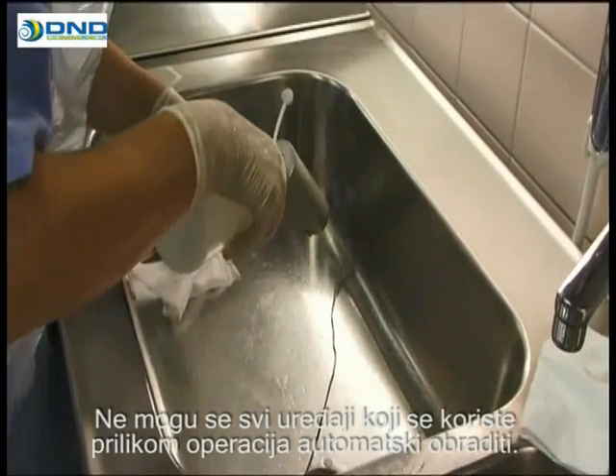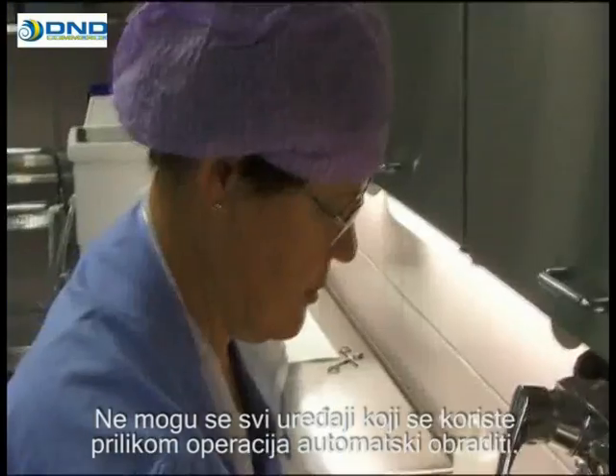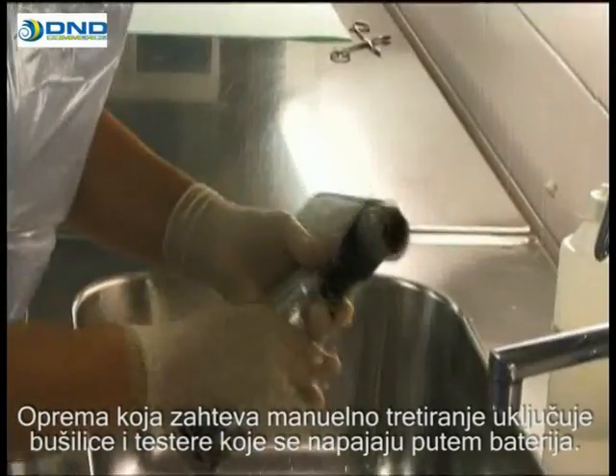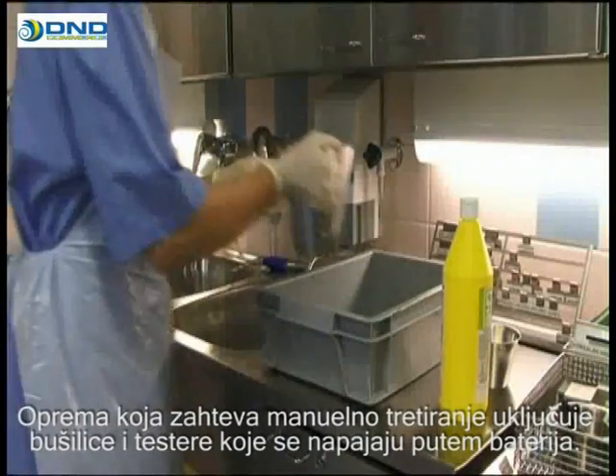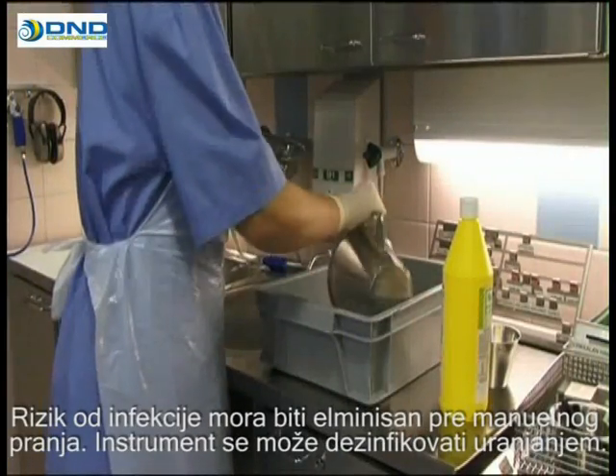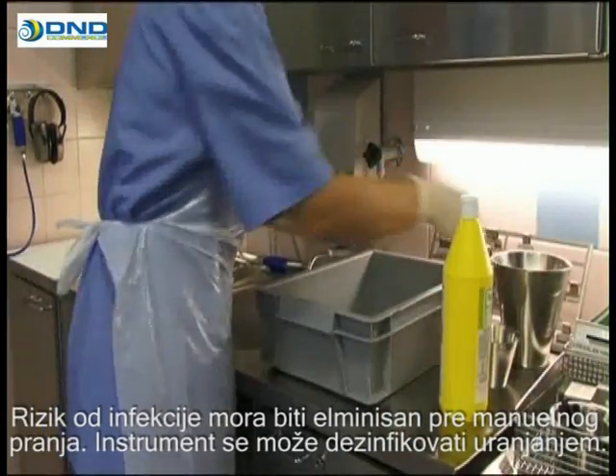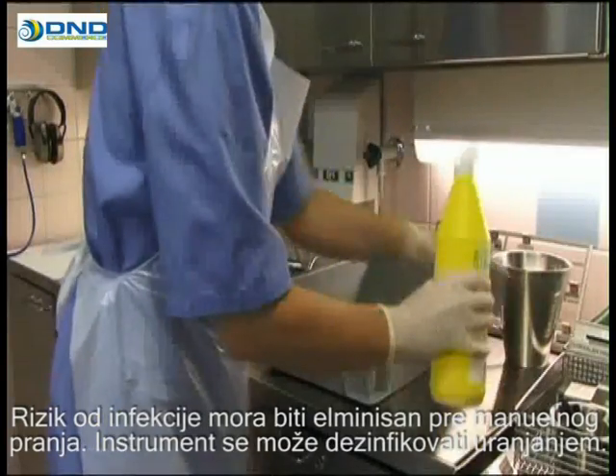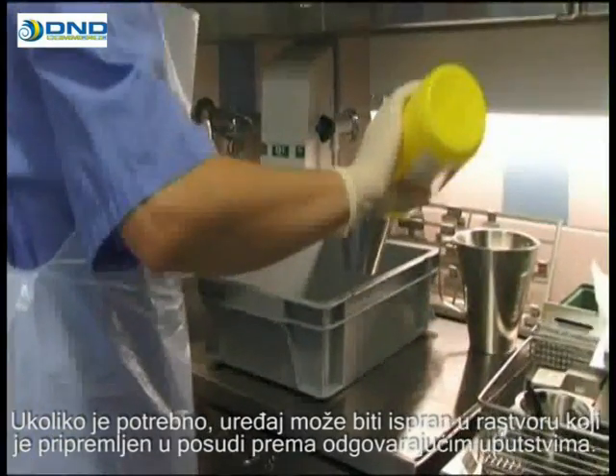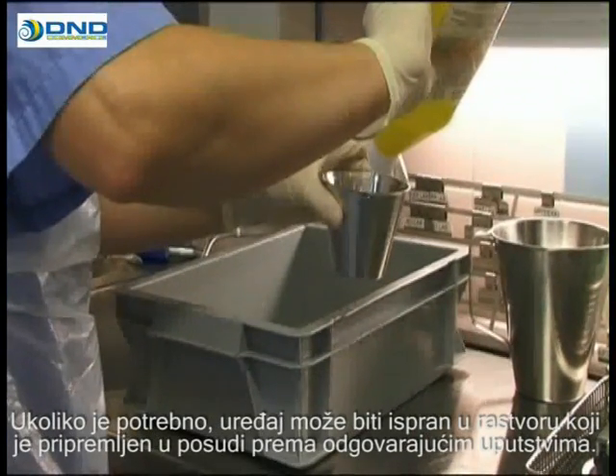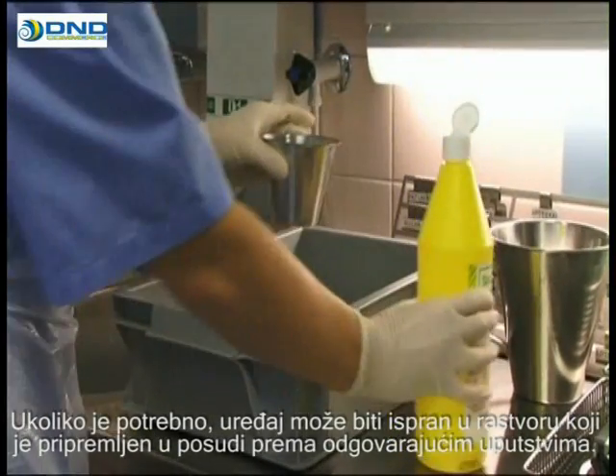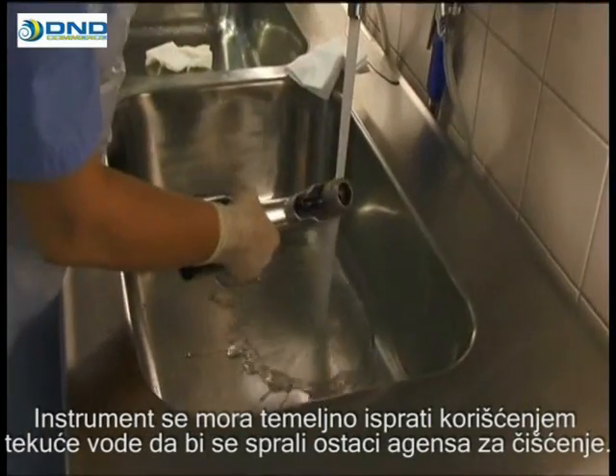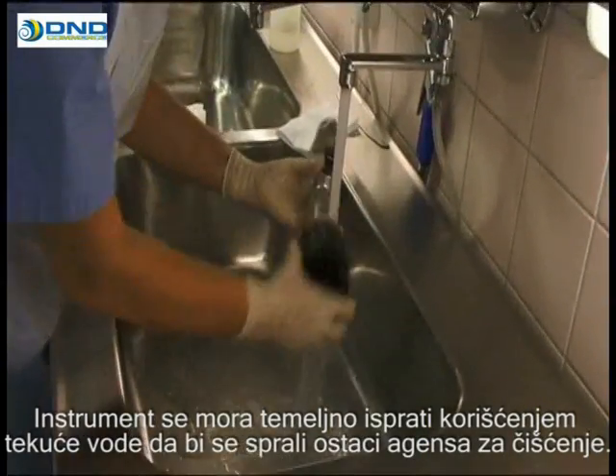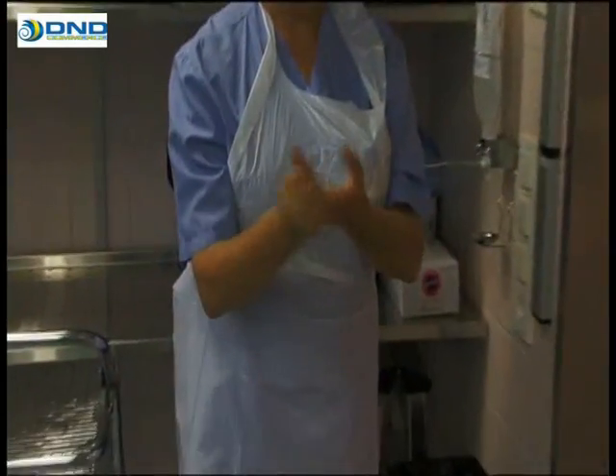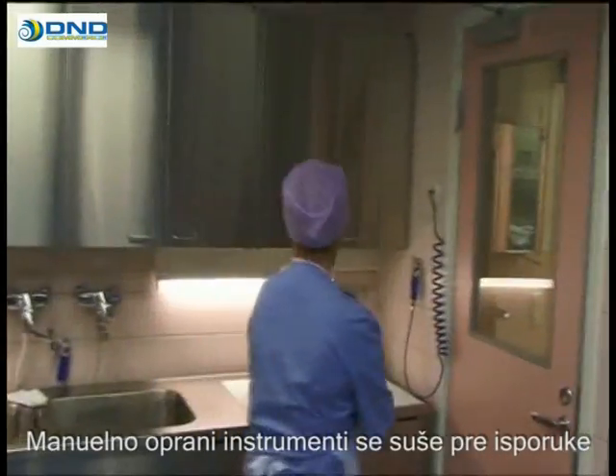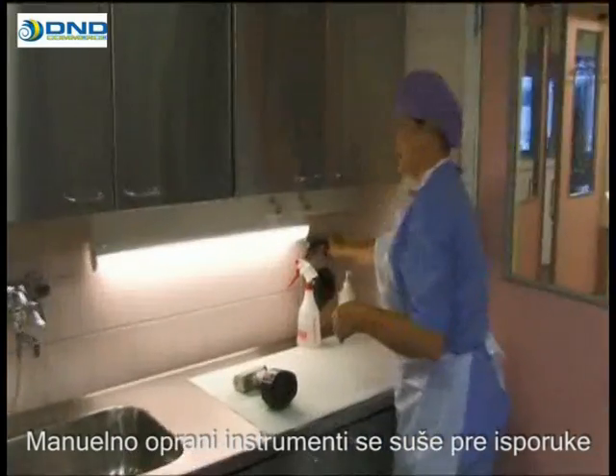Not all instruments used in operations can be processed automatically. Equipment that requires manual treatment includes battery-powered drills and saws. Risk of infection must be eliminated before manual washing. The instrument shall tolerate disinfection by immersion. If necessary, the instrument should then be washed in a solution that is prepared in a basin according to instructions. The instrument is flushed thoroughly, using running water to carefully rinse off the cleaning agent. Manually washed instruments are dried before delivery.